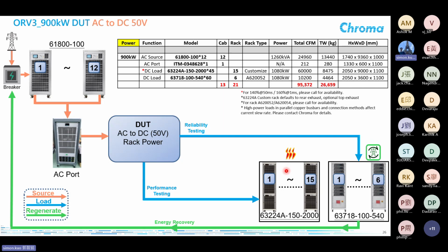If they want to do long-term testing, maybe running for hours or days, even months, it is recommended to use our regen load. By doing so, the energy drawn from the DUT will be regenerated back to the grid, so it can be reused by the machines or other equipment in the factory. Since there is a lot of energy running in this kind of situation, there are two things that need attention. One is that the total CFM, meaning the airflow, must be sufficient to fulfill the heat dissipation of all these machines.